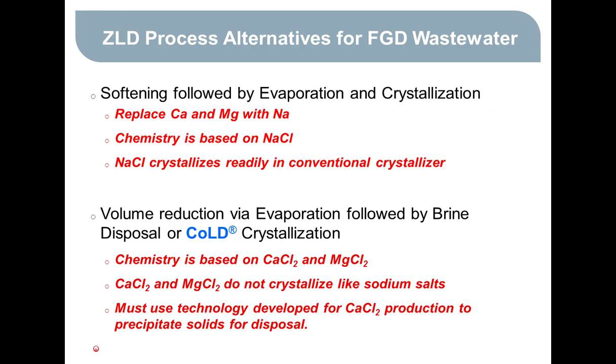So for FGD, we tend to have a different flow scheme or ZLD scheme than we do for cooling tower blowdown. There's really two alternatives. One is to just take the calcium and the magnesium out of the FGD purge water. It causes so many problems in the evaporator and crystallizer that it's easier to just remove them up front and replace the calcium and magnesium with sodium. That's basically what lime soda ash softening is. You use lime to precipitate out the magnesium and soda ash to precipitate out the calcium, and you're left with basically a sodium chloride solution. And that's pretty easy to crystallize out in a conventional crystallizer.